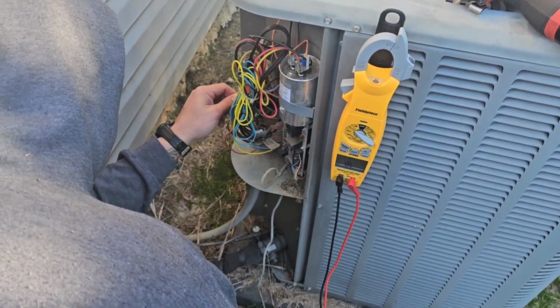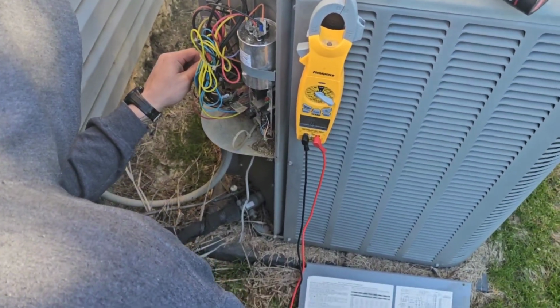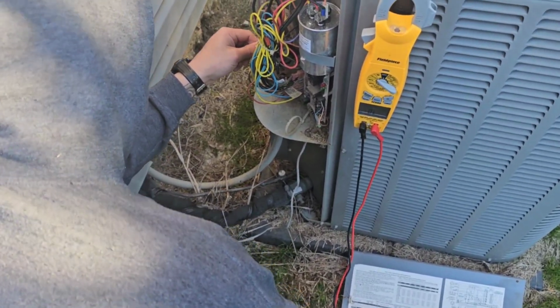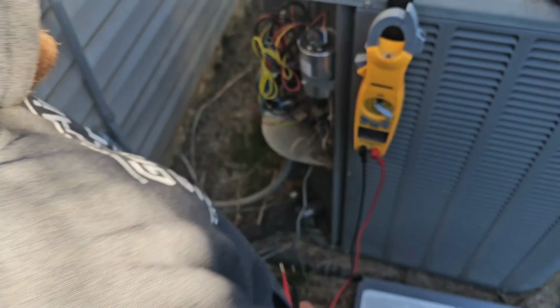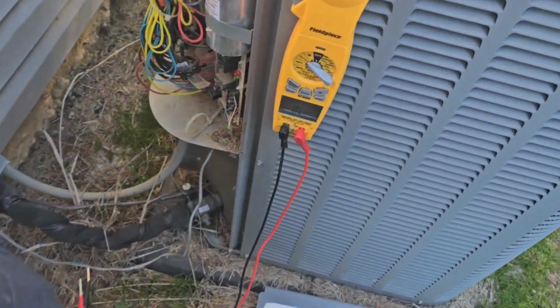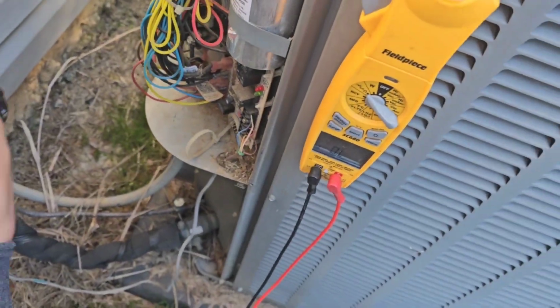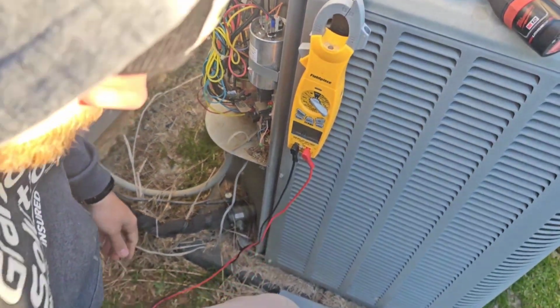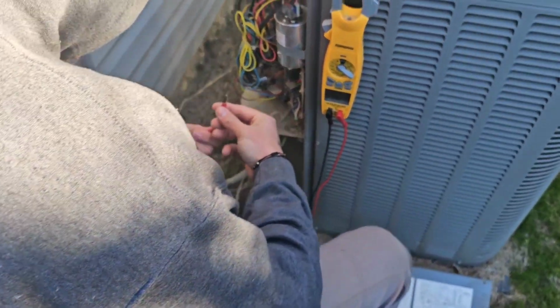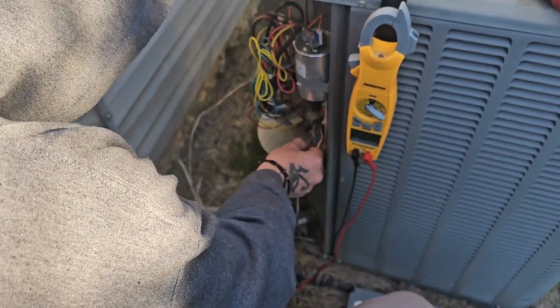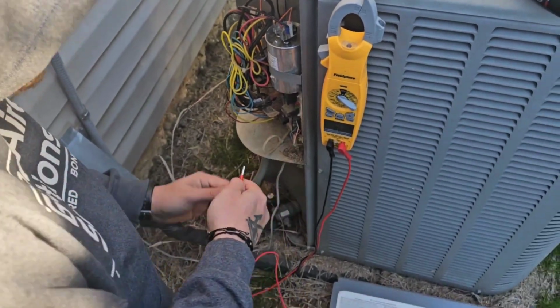Now, because I think that was the issue. They have both wires colored the same, which is weird. Normally you'll see like a yellow on one side and a brown or some other color on the other. So now put your jumper back on Y1 and put it to the other side of the contactor that has no wire on it. It should click in.